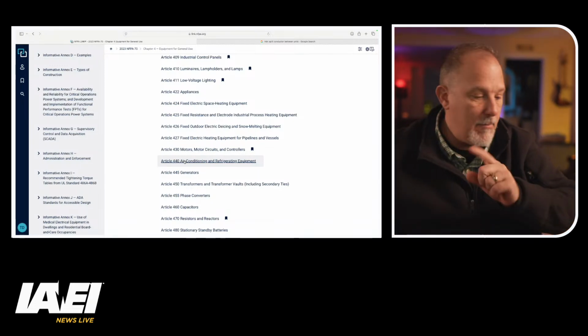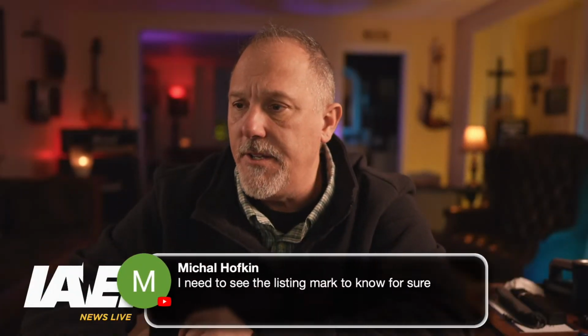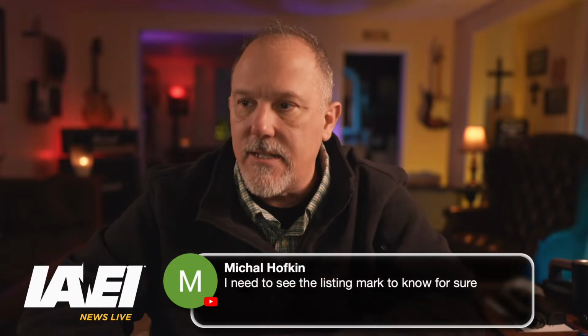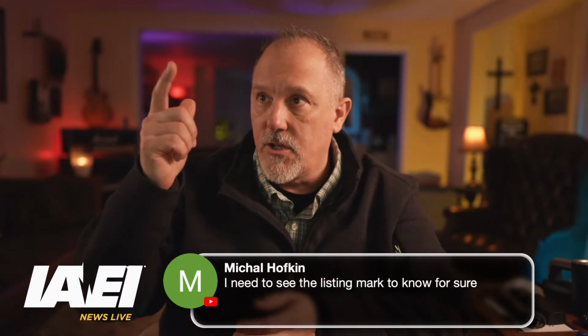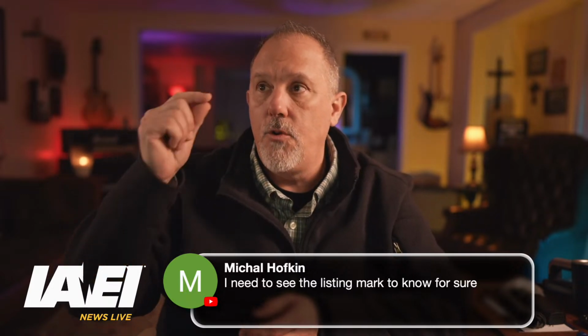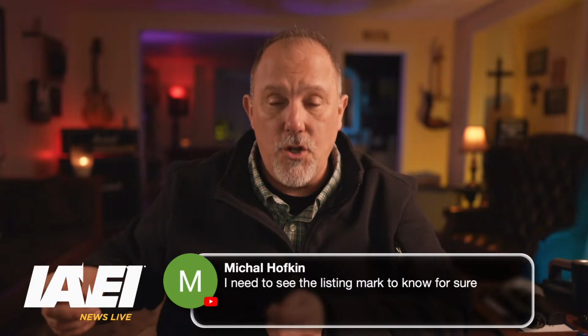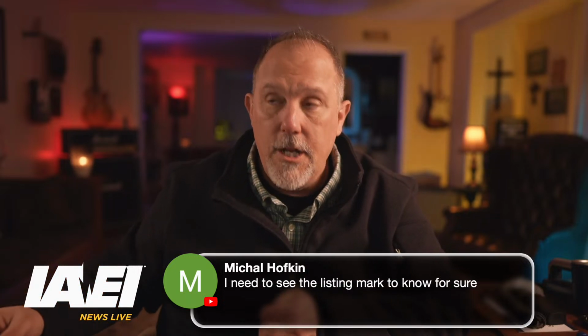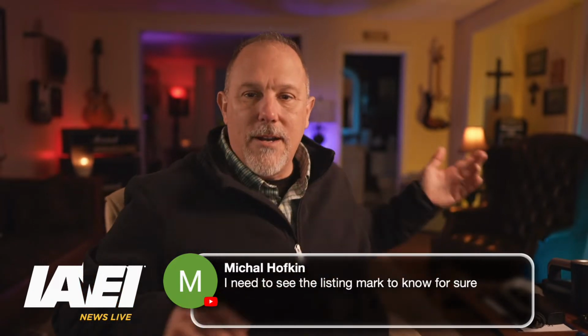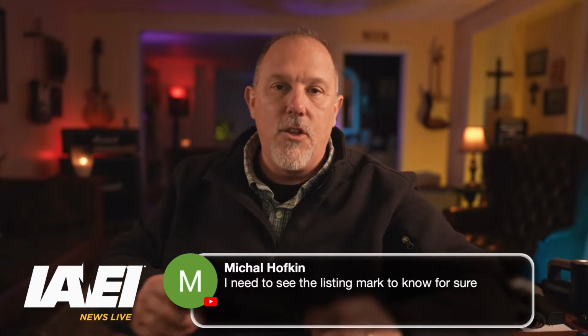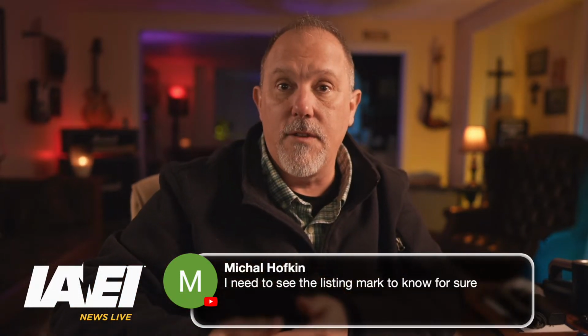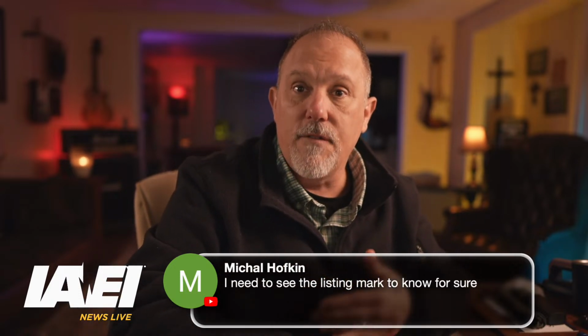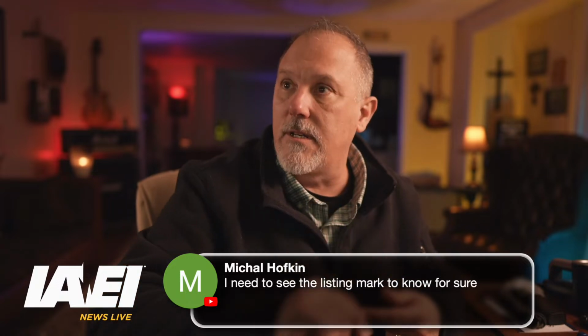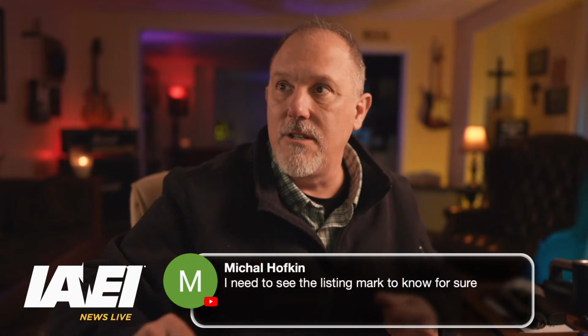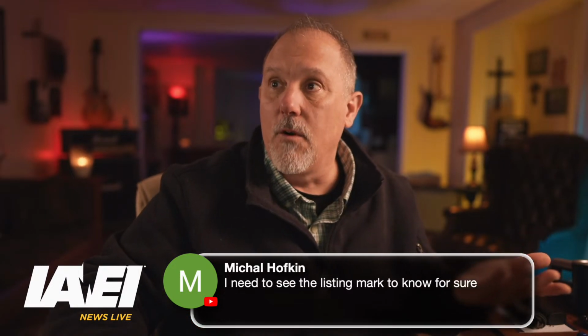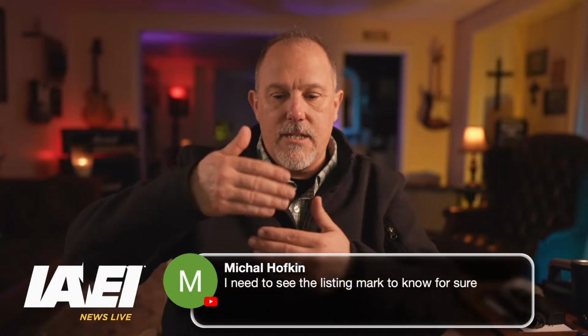Then what David and Michael pointed out was that he needs to look at the listing mark, and go back to, as long as you know it's an air conditioning unit, look at the listing mark to determine what UL standards it's listed to. You could go to Product IQ to understand the standards and the installation requirements, and see if there's anything it speaks to regarding that conductor. Then go to the manufacturer's instructions, but you'd also want to look at the requirements in 440 as well. So it's a roadmap.